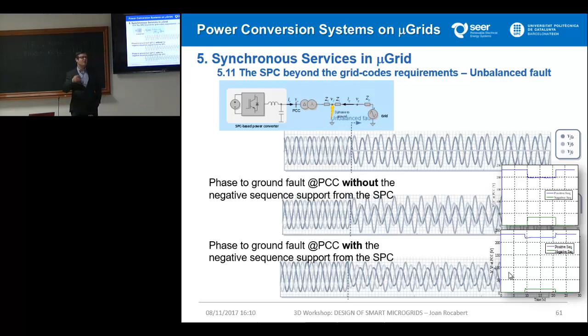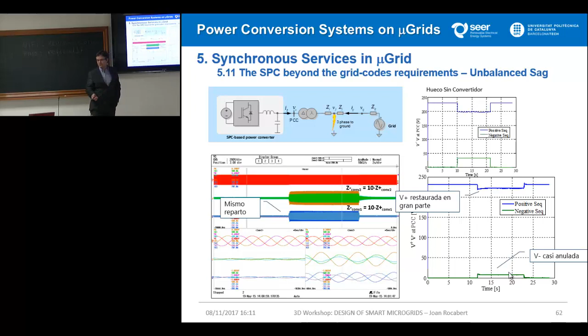Again, we have experimental results. We get an unbalanced sag, and you can see the large transient here, and this is the stable voltage. Then, in that stable voltage, between those two points, we make the unbalanced condition: we make a short circuit on one of the lines. Because the grid impedance was big enough, our converters, each one at a different power, were able to restore the voltage conditions. Finally, the point of common coupling supplying our loads is again showing sinusoidal waveforms.